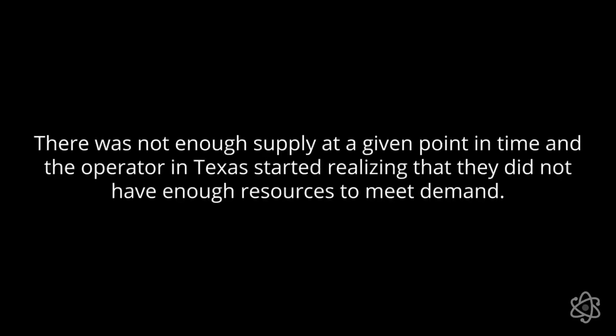They have to keep the balance of supply and demand exactly matched at every single second. And for these, they have several look-ahead periods. They usually have a day ahead and an hour ahead, and then even a five minute ahead. And they started realizing that their forecasts for the demand side were also pretty off. That created a further mismatch between the supply that's already curtailed and demand that's not even at a regular level. It was much higher. And because of diversion of resources towards heating, these two started creating a problem in which there was not enough supply at a given point in time. And the operator in Texas started realizing that they did not have enough resources to meet demand.